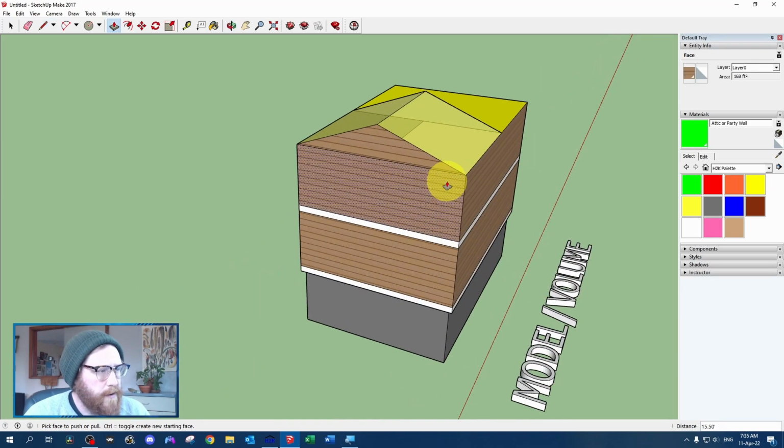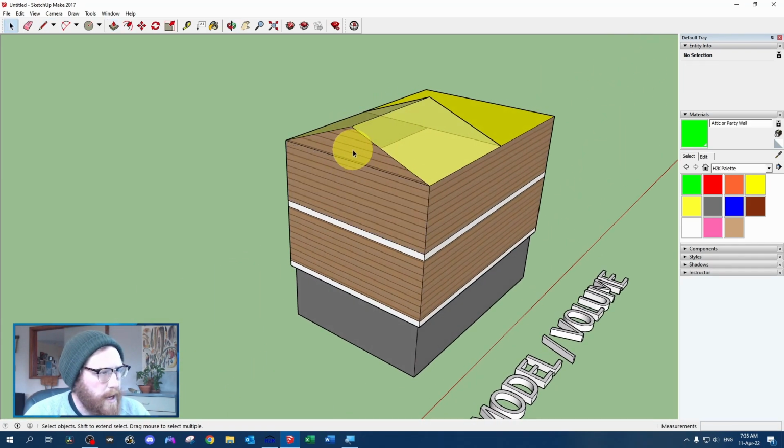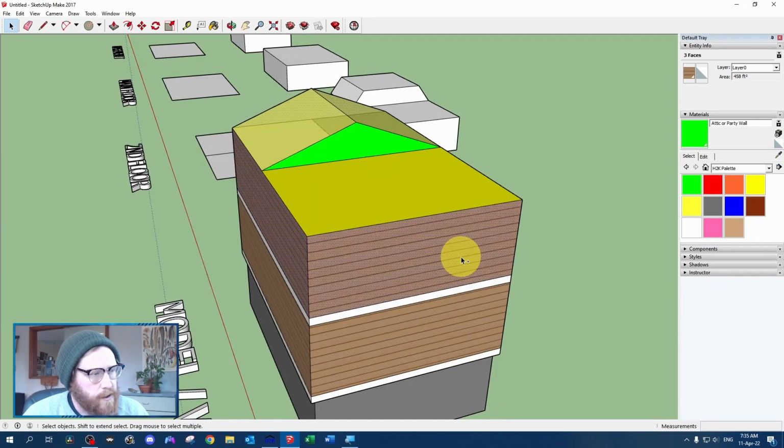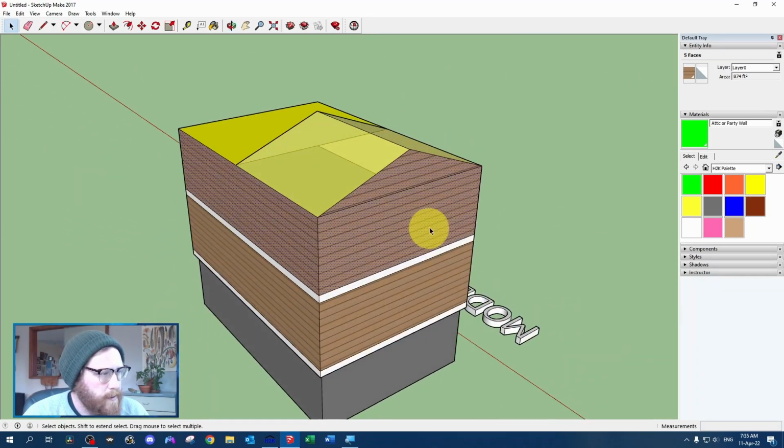And then for entering in Hot2000, if this bit of gable is the exact same makeup as this wall, so if they have the same exterior finish, same insulation, same interior finish, same studs, everything, we can combine these areas together. And an easy way to do that, so if you want to do the whole second floor as its own wall, you can see here, normally it'd be 8 feet times the entire perimeter, but because of the gable, we need to get an average height, so you just control click all the way around.